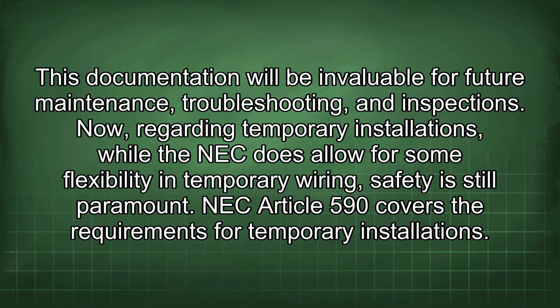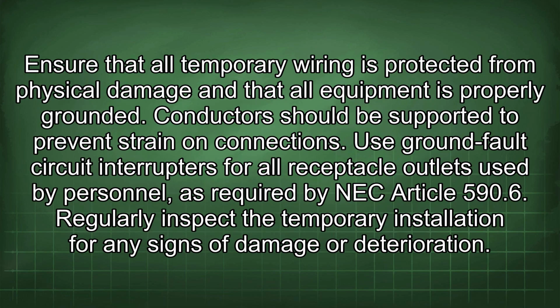Now, regarding temporary installations, while the NEC does allow for some flexibility in temporary wiring, safety is still paramount. NEC Article 590 covers the requirements for temporary installations. Ensure that all temporary wiring is protected from physical damage and that all equipment is properly grounded. Conductors should be supported to prevent strain on connections.